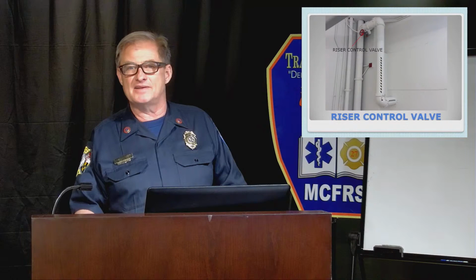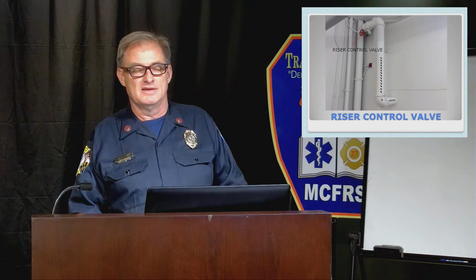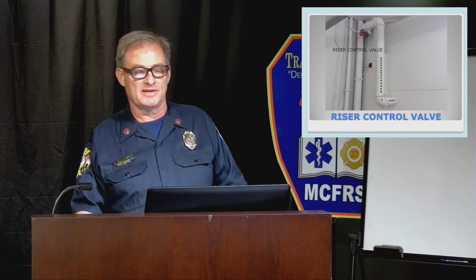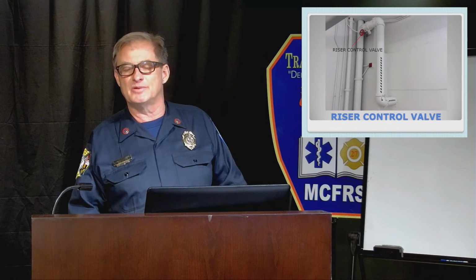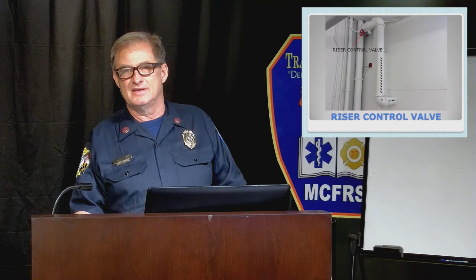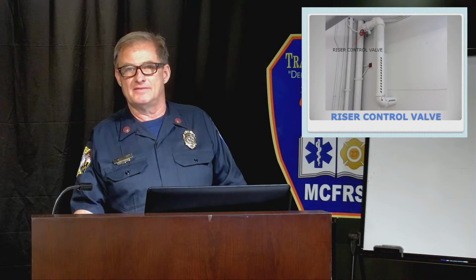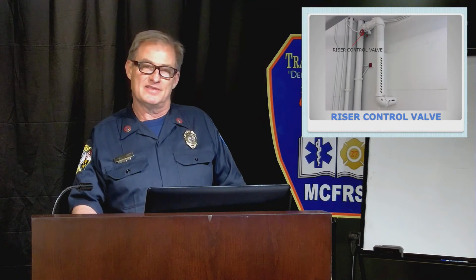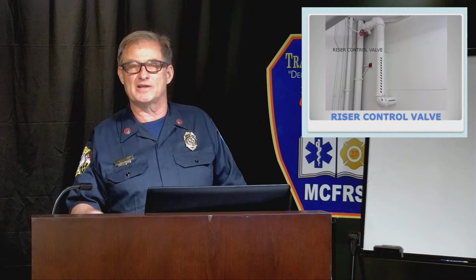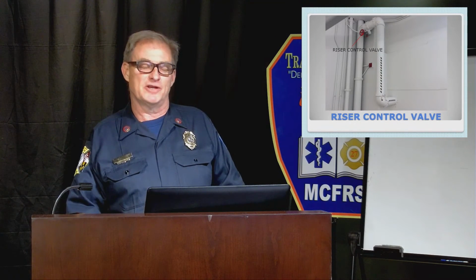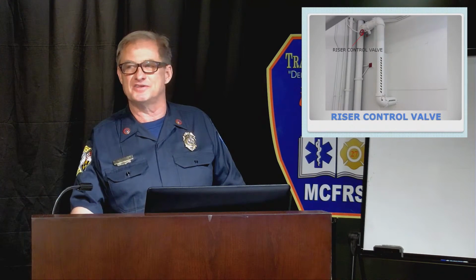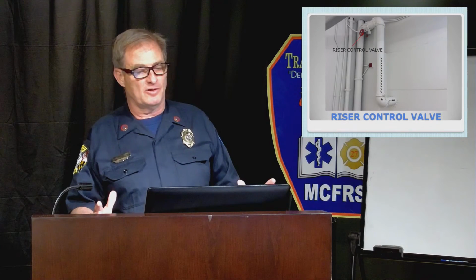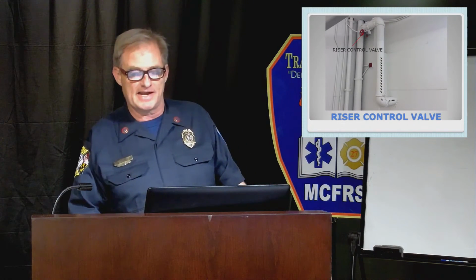In my investigations, I actually had a case in Wilmington at one of the bank buildings. A fitting at the top of a riser gave way. It had been there for 7 or 8 years. It gave way during a fire pump test, and it did $6 million of water damage. So that was significant. We actually went through that building and examined every single fitting in the building, and we found about 20% of the fittings were not torqued to spec. And that's obviously a problem. What we also found is, interesting enough, we could kind of track that lack of attention to detail to one sprinkler crew. They had 3 crews working, and we could kind of track one crew that didn't do their diligence in putting these fittings together. So they lived for a long time, but when they're called on with a dynamic force, they can definitely give way.